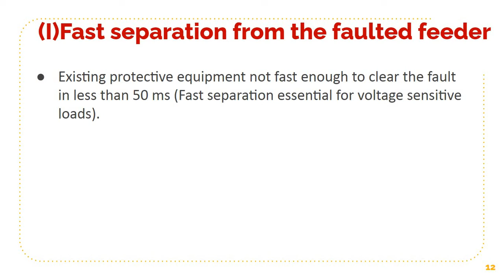So the existing protective equipments are not fast enough to clear the fault in less than 50 milliseconds. But this separation of less than 50 milliseconds is essential for voltage sensitive loads, especially electronic equipments or PLCs. A medium voltage breaker requires 3 to 5 cycles to interrupt the circuit after receiving the trip signal. One cycle, you must be knowing, is around 20 milliseconds. So 3 to 5 cycles means around 100 milliseconds. So a medium voltage breaker requires approximately up to 100 milliseconds to separate after getting the trip signal. This 100 milliseconds is not fast enough, and it may damage many voltage sensitive loads.